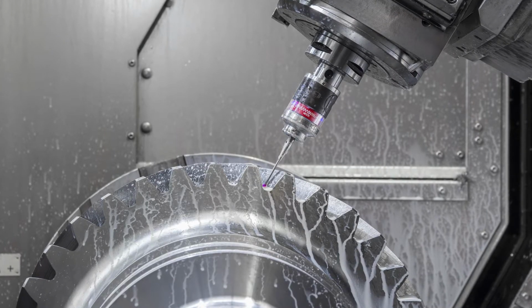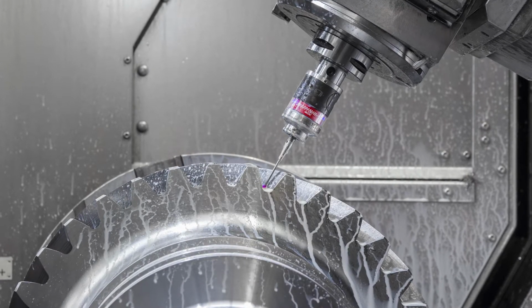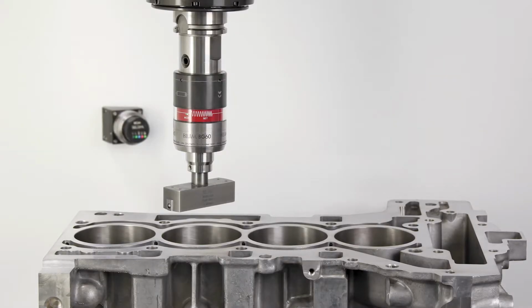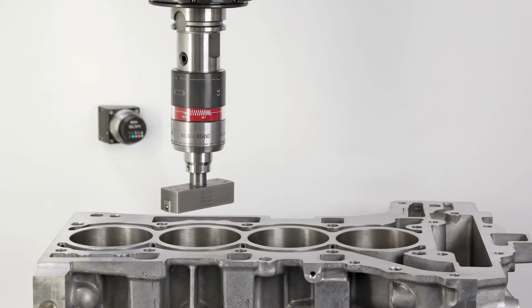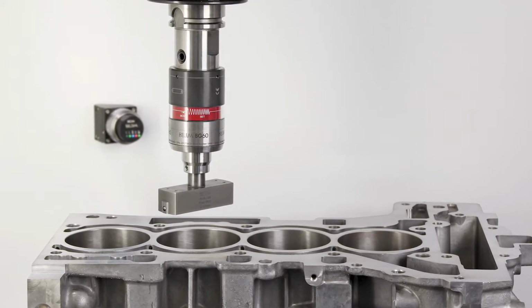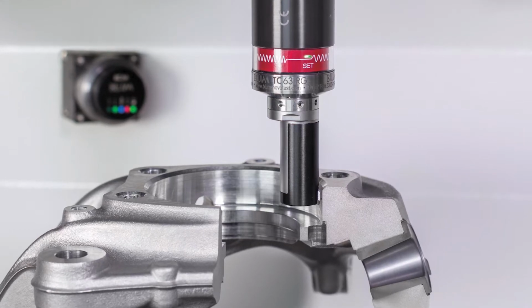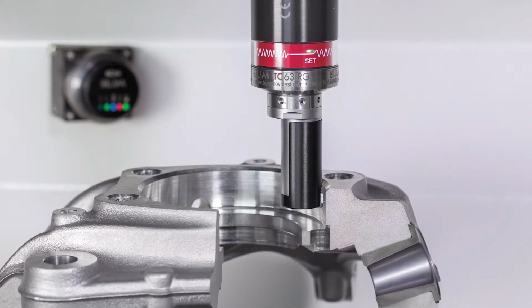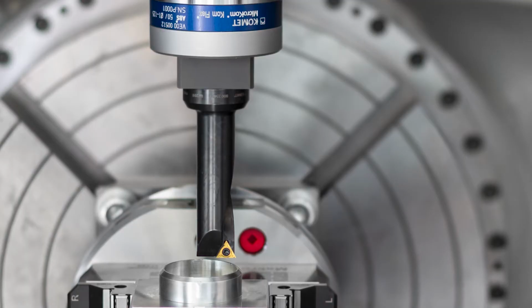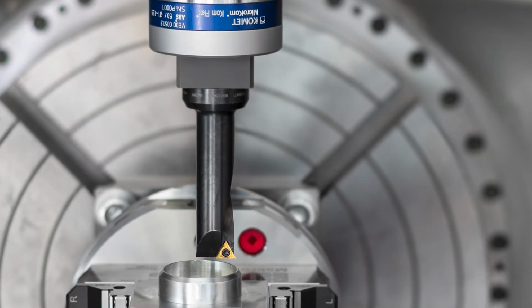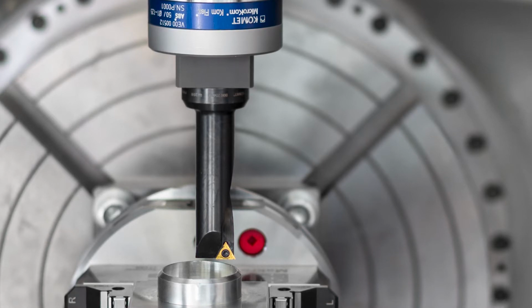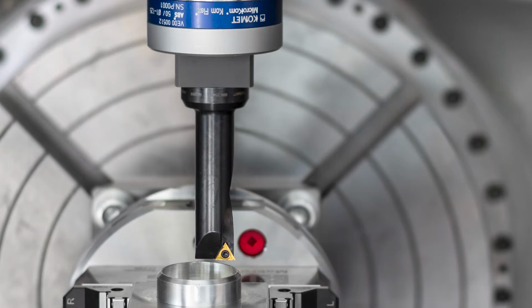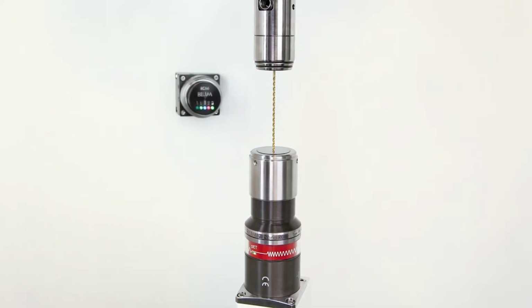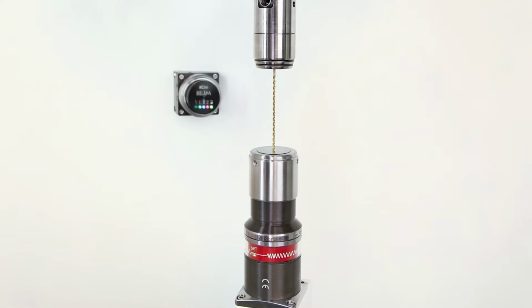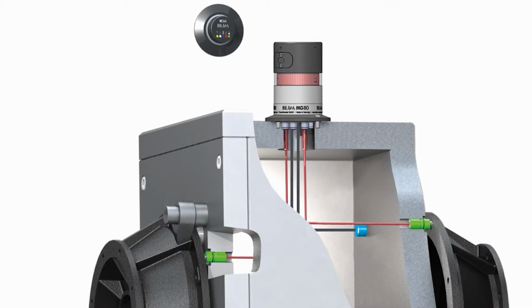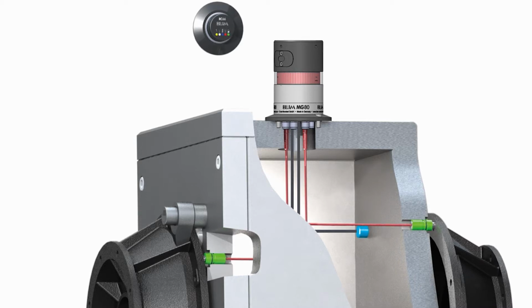The TC64 Digilog is used for scanning and monitoring any contours, but more on that later. The BG series includes machine-independent bore gauges for determining internal diameters greater than 3 mm, the RG roughness testing device with visualization and evaluation on the machine control system, the KOMET fine spindle tool. This is set to the required dimension by the RC66 receiver after determining the diameter using a probe or bore gauge. The Z-Nano can be used for tool length measurement, monitoring and concentricity testing. The MG80 is used to determine the workpiece temperature and the clamping pressure in real time.